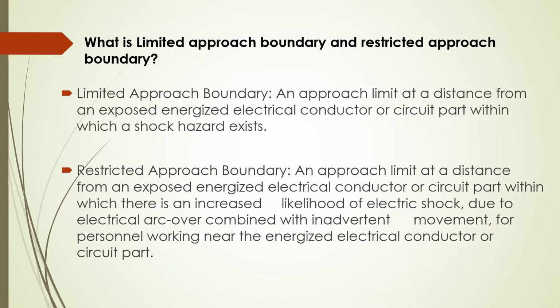What is limited approach boundary and what is restricted approach boundary? Limited approach boundary: an approach limit at a distance from an exposed energized electrical conductor or circuit part within which a shock hazard exists. Restricted approach boundary: an approach limit at a distance from an exposed energized electrical conductor or circuit part within which there is an increased likelihood of electrical shock due to electrical arc over combined with the inadvertent movement of the personnel working near the energized electrical conductor or circuit part.